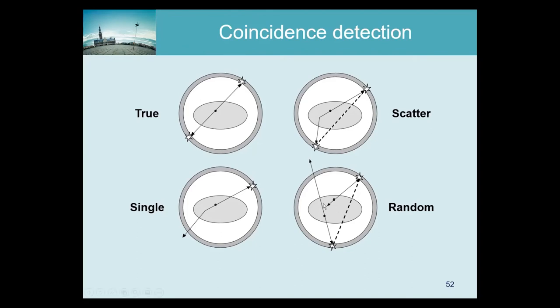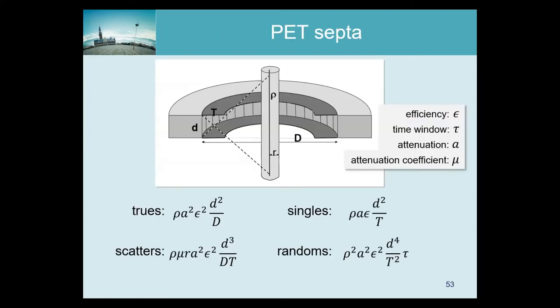A large number of singles causes dead time problems. Another problem is that if two singles arrive simultaneously, they are mistaken for a coincidence — a random event — producing a false coincidence line that may lie outside the patient. Randoms typically follow a very uniform spatial distribution. Some calculations show how PET system geometry affects the relative amounts of trues, scatters, singles, and randoms acquired.